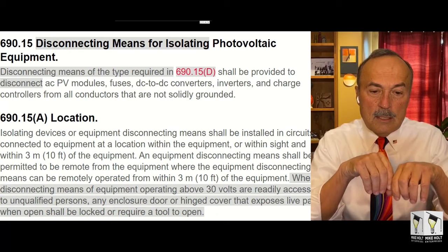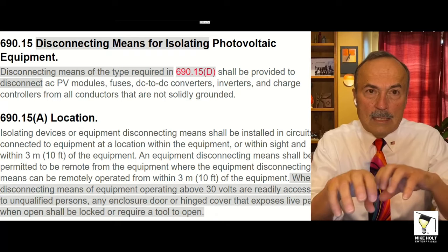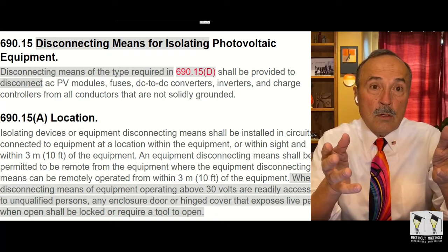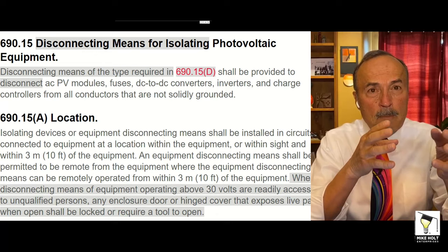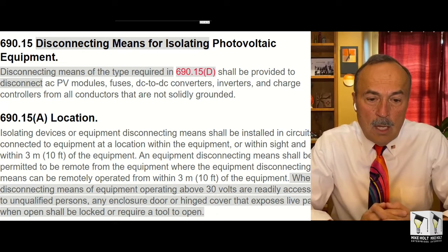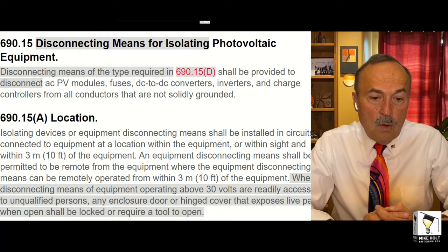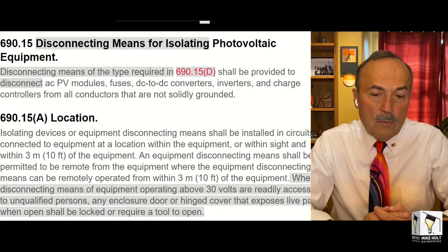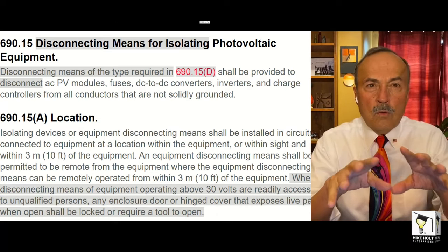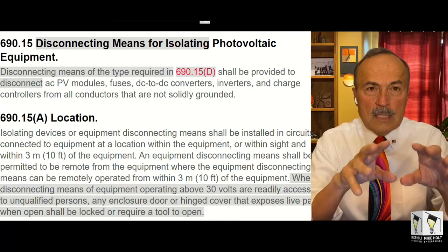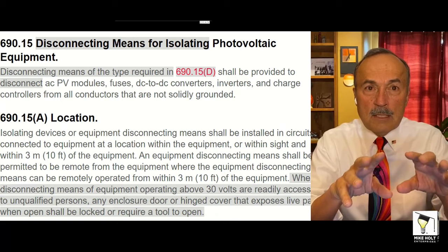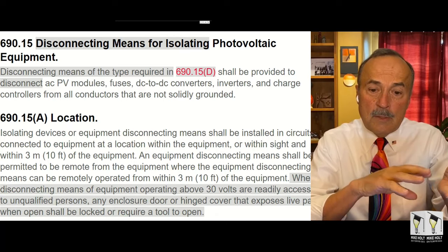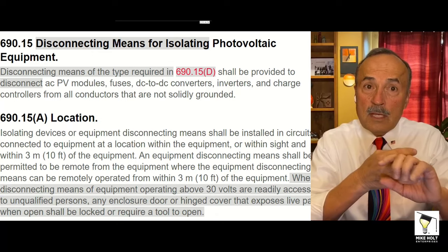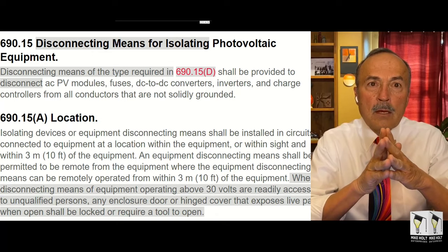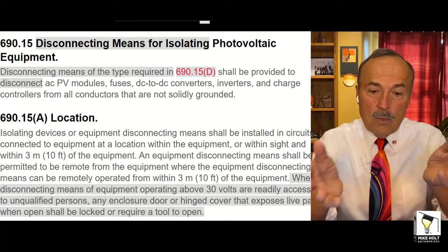So equipment disconnecting means are not required to be readily accessible, because this equipment might be on a roof or might be in a location. So it's going to have to be accessible from the equipment. An equipment disconnecting means shall be permitted to be remote from the equipment where it can be remotely operated from within 10 feet of the equipment. I don't know what kind of solar equipment it is, but your PV system equipment must have a disconnecting means either within it or within 10 feet of it, and it has to be within sight. If it's not within it, within 10 feet or within sight, then you can control it remotely within 10 feet of the equipment.